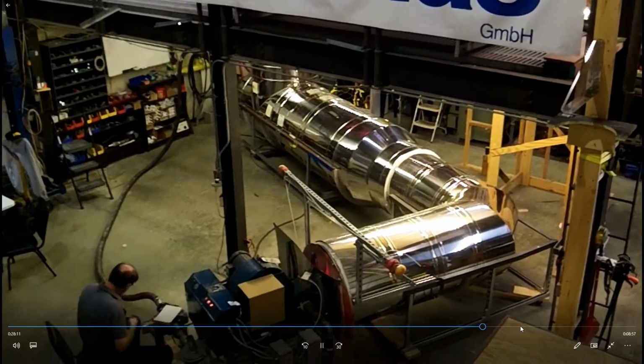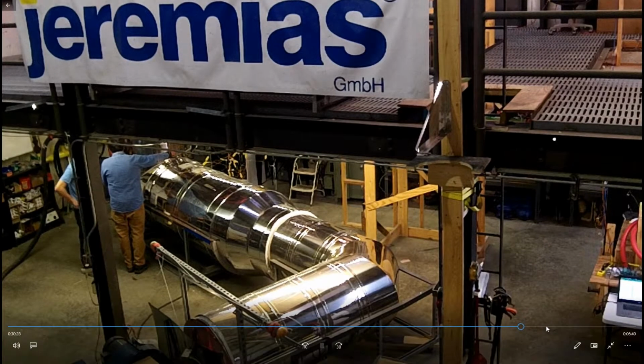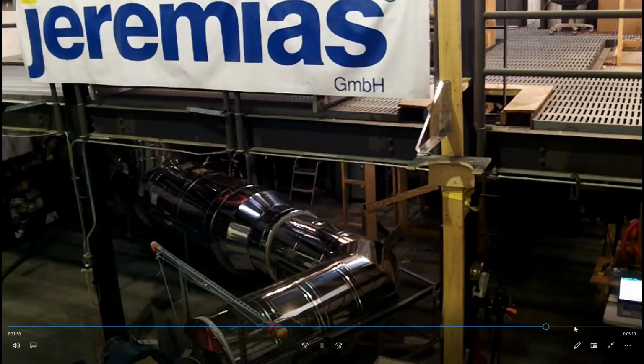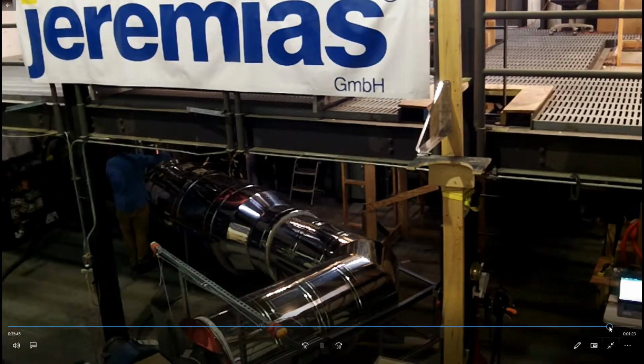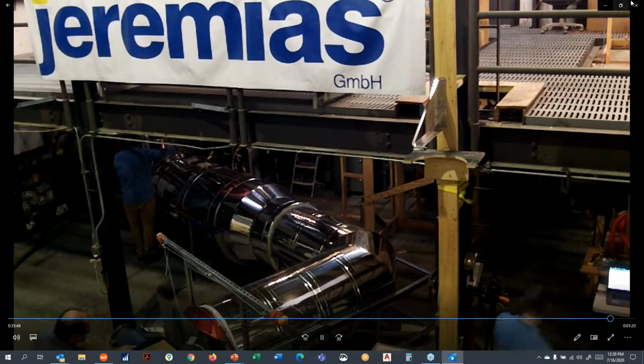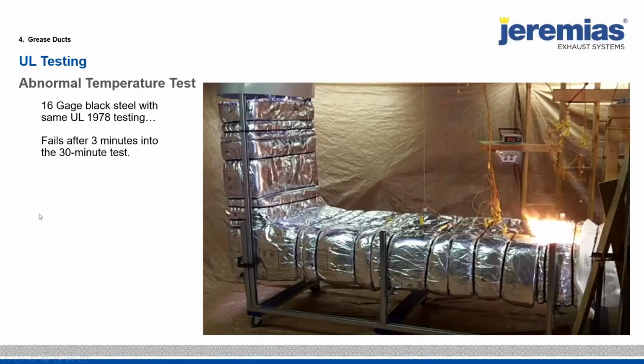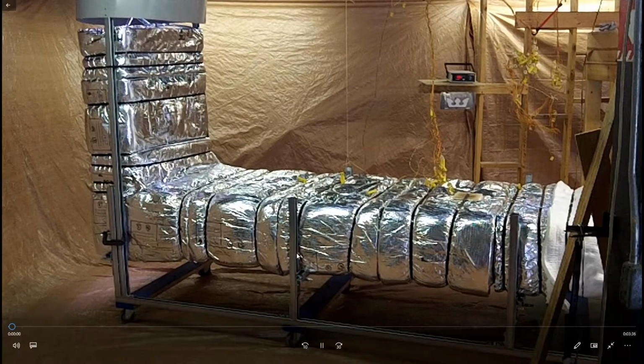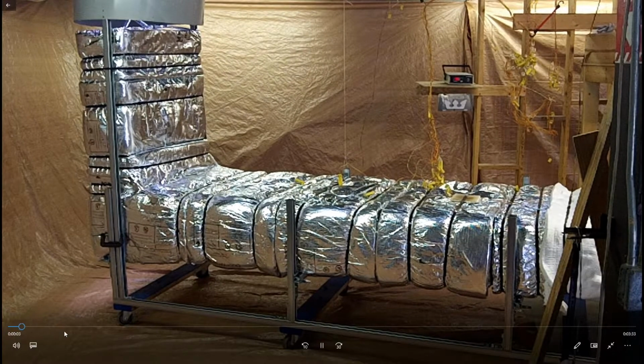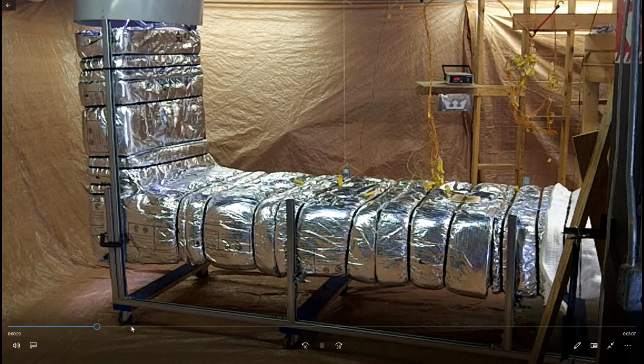So we want everyone to understand how long this 30 minutes is. That's why we want to go through this quickly. Because what we did is we thought we would take a carbon steel system and put it through the same test. Now that video is much shorter. We like to talk to people one-on-one so they can make guessing, but we actually did a 16-gauge black steel duct system. We double wrapped it with fire wrap that's required by the ASTM E2336. And this video is much shorter. This video is about 3.5 minutes long. And what I want everyone to focus on is looking at the middle of the flat horizontal ductwork. Watch how it starts to collapse.